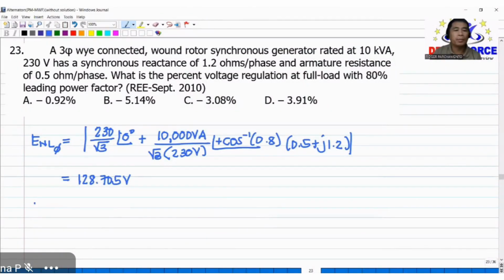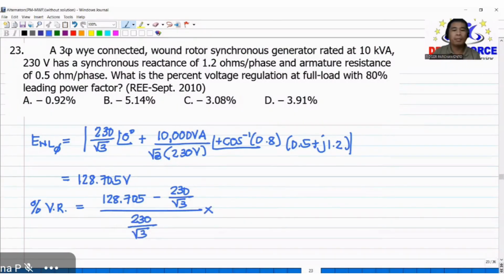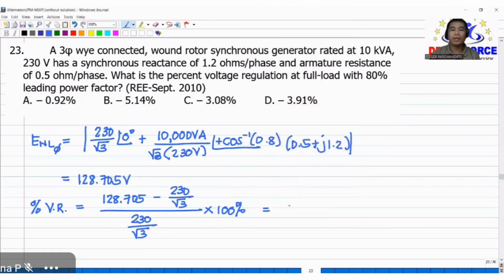So per phase. Therefore, what is the percent voltage regulation? So that will be 128.705 minus 230 over square root of 3, all over 230 divided by square root of 3, multiplied by 100%. So the percent voltage regulation is negative 3.08%. Negative 3.08%. So letter C. That is number 23.